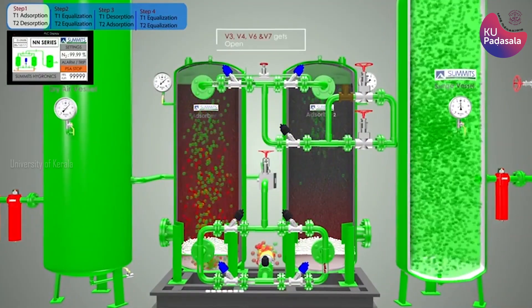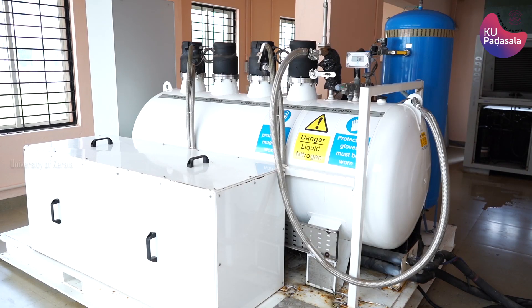Finally, the pure gaseous nitrogen is passed through a cryo refrigerator consisting of a cold head, a helium gas compressor package, and a pair of stainless steel flexible helium lines. The cold head is mounted into the top of the liquid tank Dewar and extends down into the neck of the liquid tank for the purpose of cooling the nitrogen entering into the liquid tank to about 77 Kelvin, that is minus 196 degrees Celsius. The nitrogen gas liquefies on contact with the cold head heat exchanger, and the liquefied nitrogen drips out through the heat exchanger down into the Dewar.